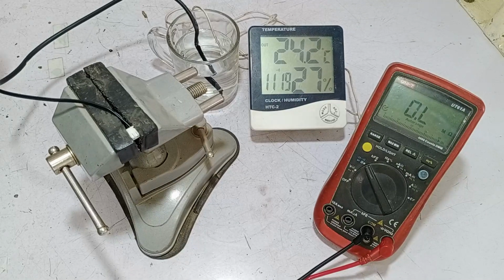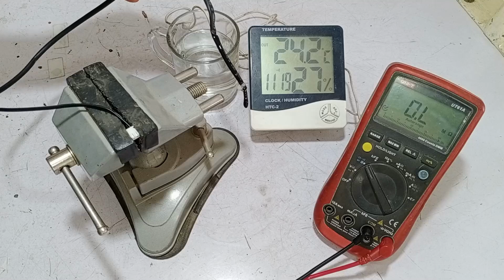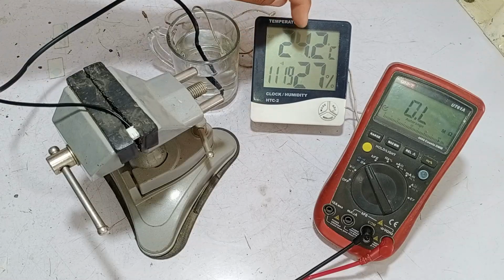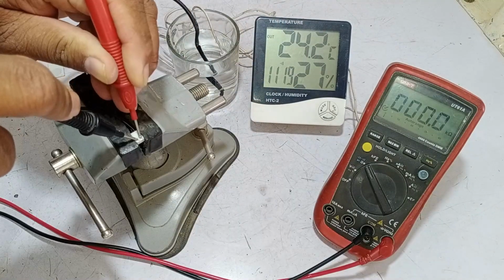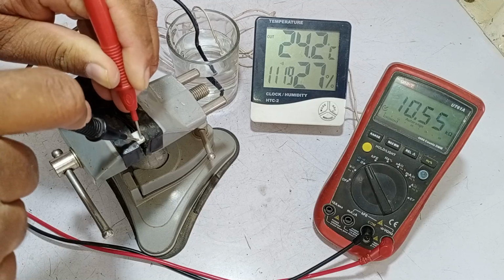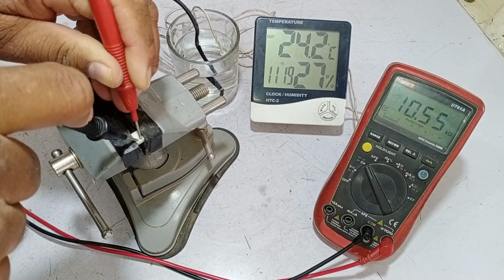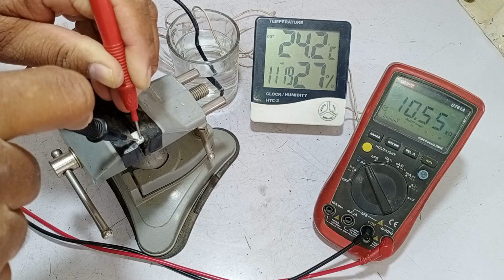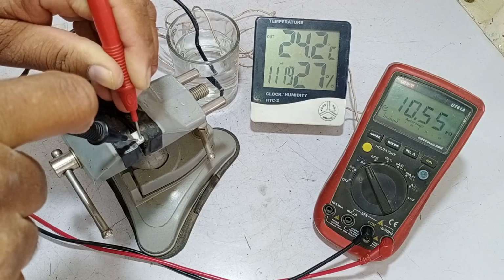Let's talk about the room temperature sensor and its correct value. Currently, the temperature is reading 24.2 degrees and the sensor is showing a value of 10.55 kiloohms. So if you install a 10 kiloohm sensor, the error will be resolved and the unit will function properly.